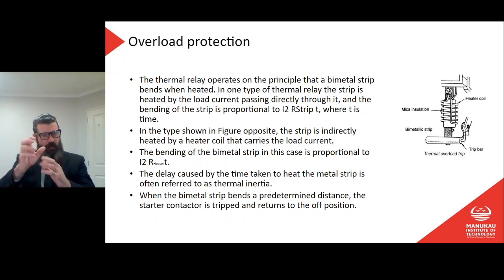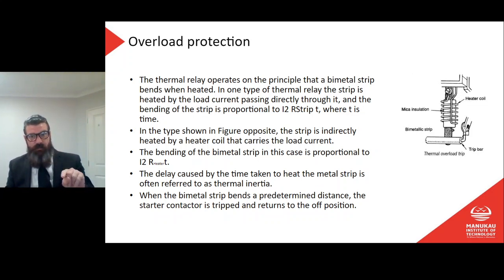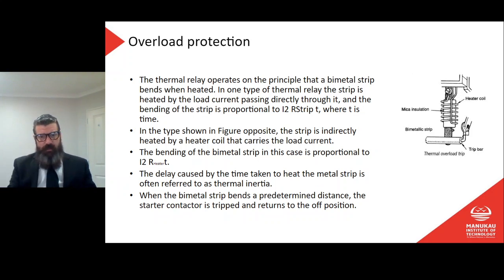You can usually find it on the contactor for that motor. Generally, a motor will be controlled by a contactor. The contactor is controlled by our push button stop start, and then each contactor will have its own little overload connected to it. But in this case, the thermal overload is going to operate in exactly the same way as we've talked about for our MCB, so I don't think I need to go into that again. You guys are welcome to read this bit yourself.